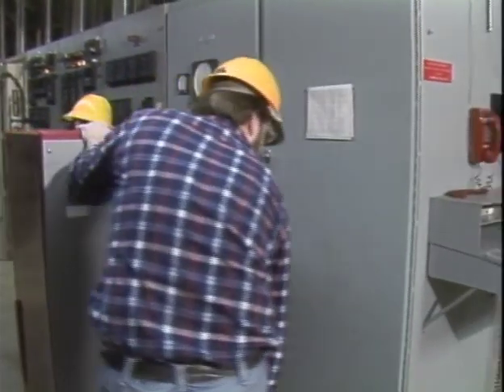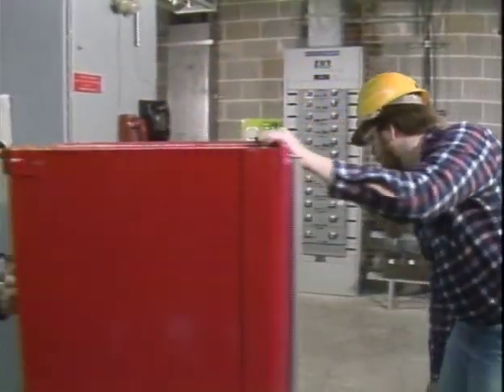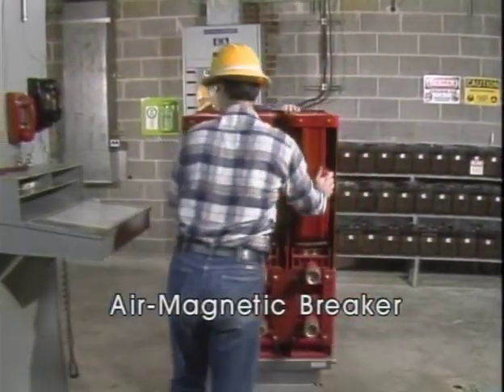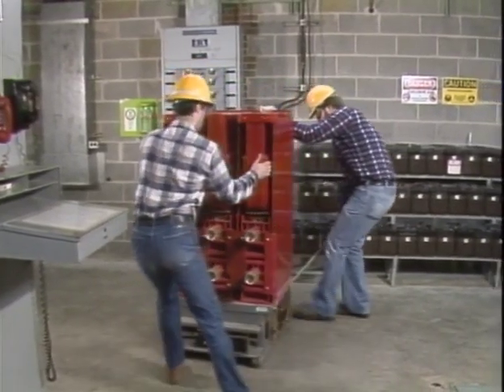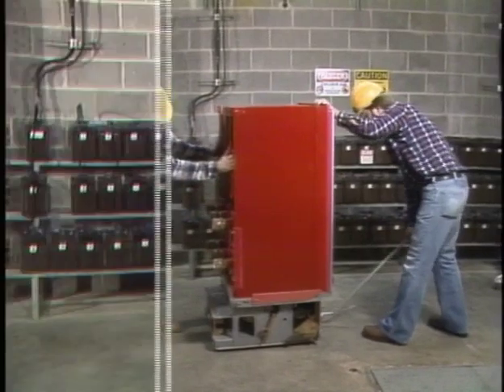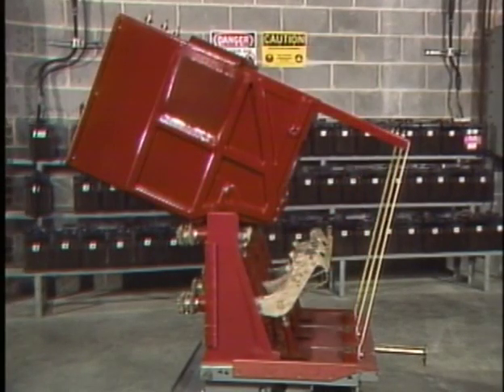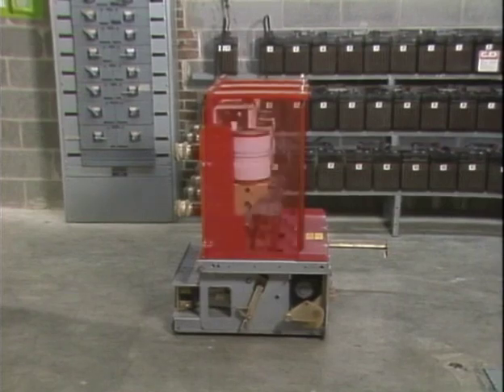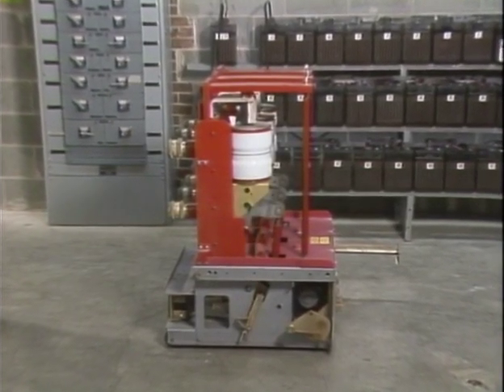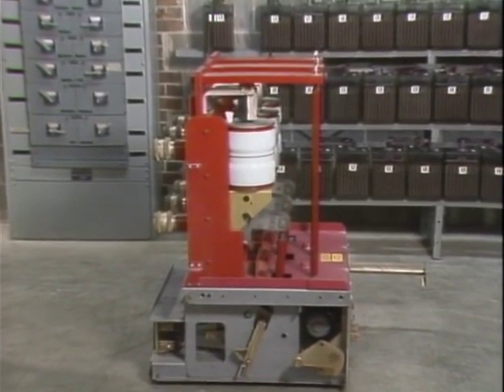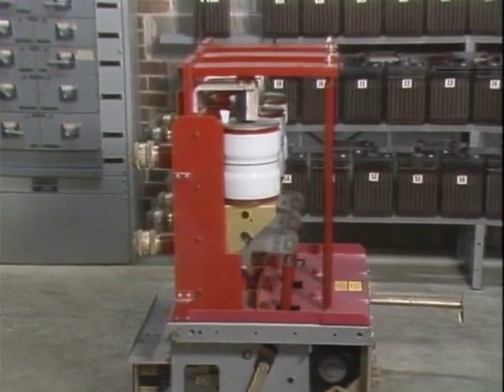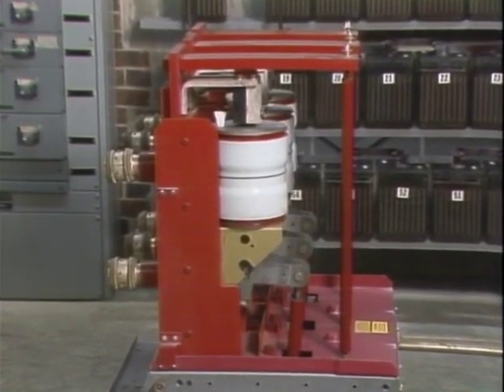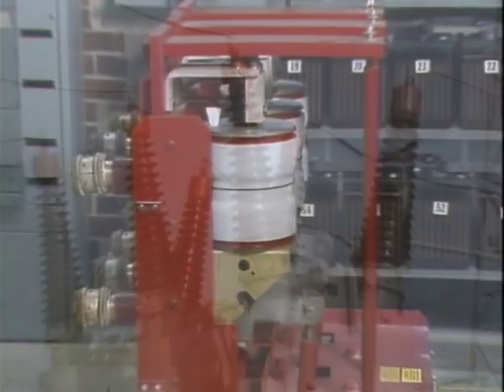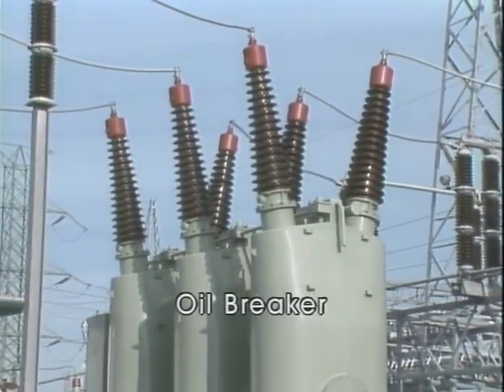There are currently 6 main types of power circuit breakers in use in electrical substations. One of these is the air magnetic breaker, which is typically enclosed in a protective metal cabinet inside a substation control house. The air magnetic breaker uses a puff of air and a magnetic field to stretch and extinguish the arc that forms when the breaker opens an energized circuit. A second type of power circuit breaker is the vacuum breaker. The contacts of a vacuum breaker are enclosed in a sealed vacuum envelope or bottle. Because the contacts open and close in a vacuum, any arcing that might occur cannot be sustained and is usually extinguished quickly. A third type of power circuit breaker is the oil circuit breaker.